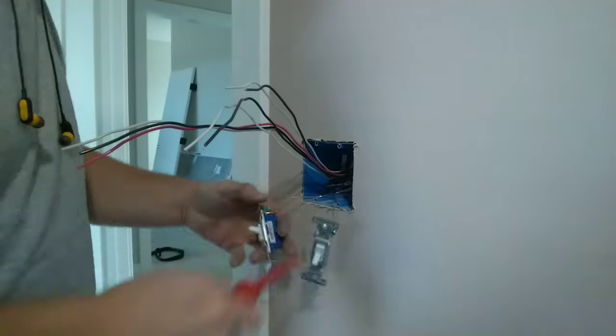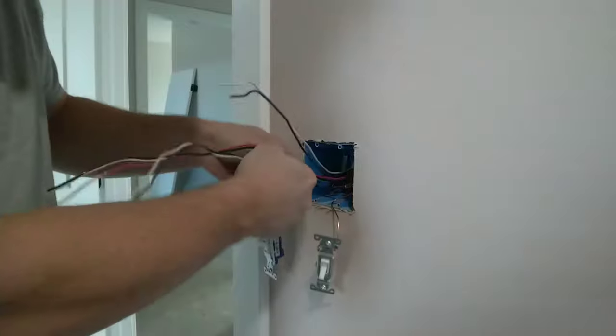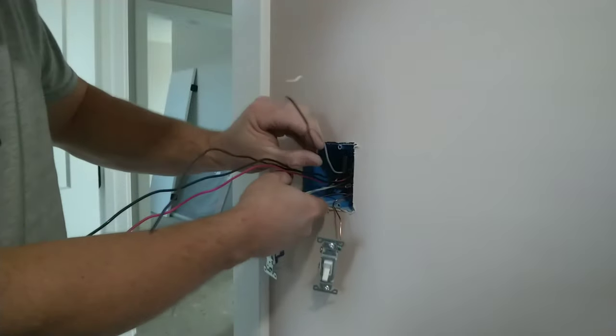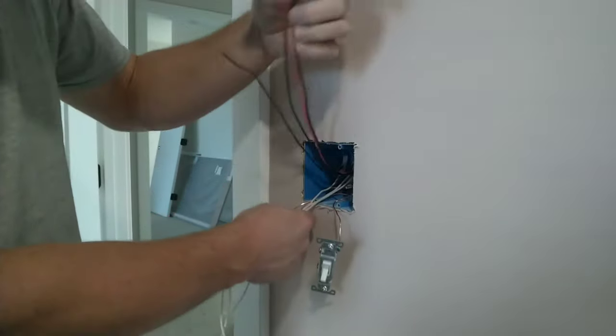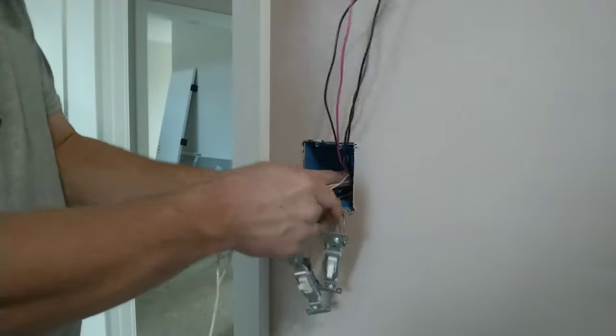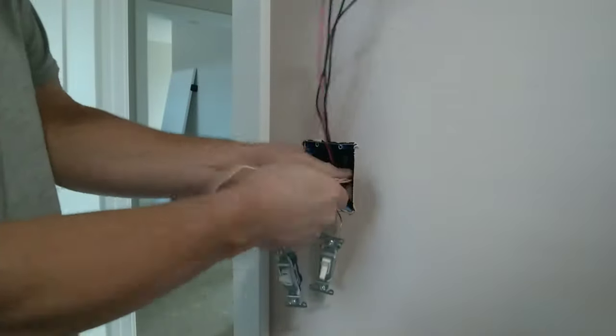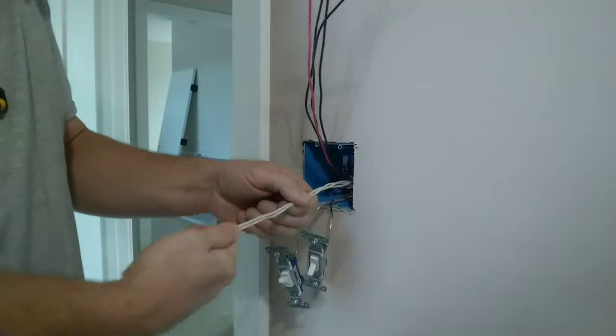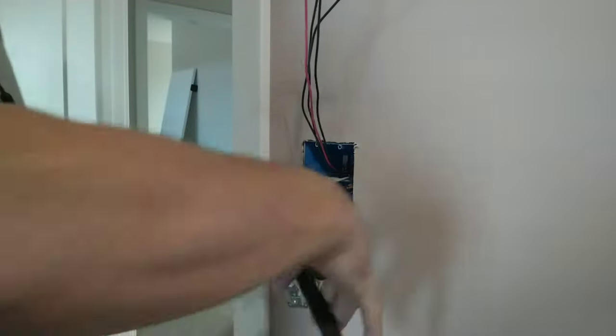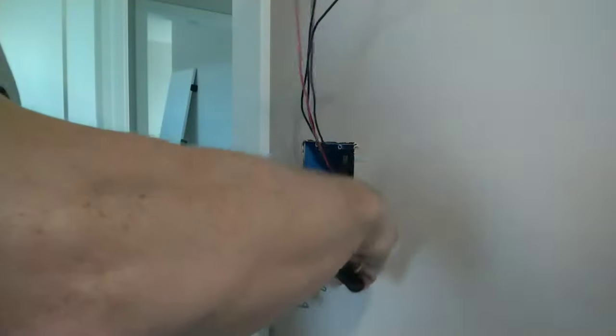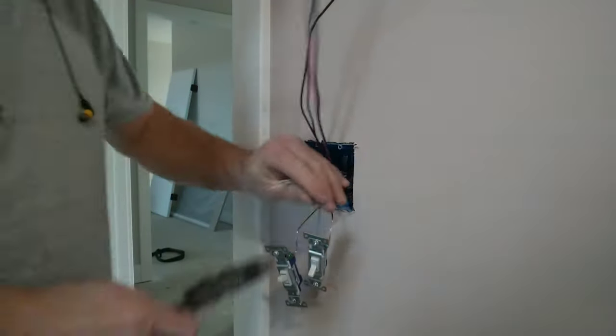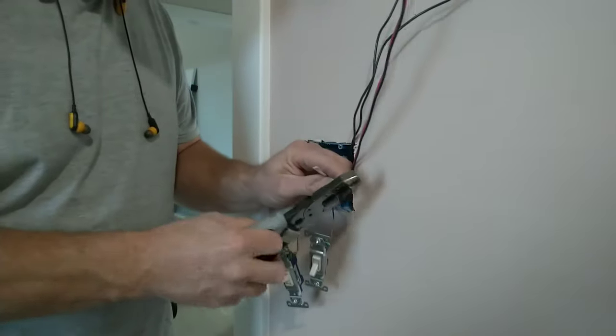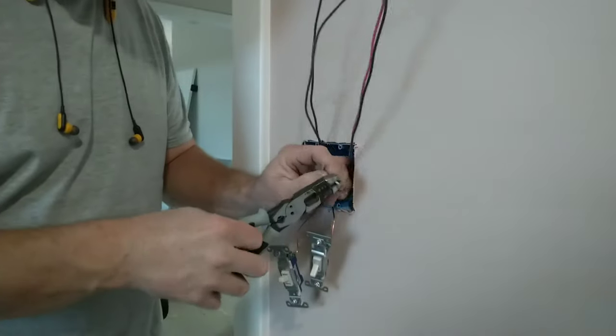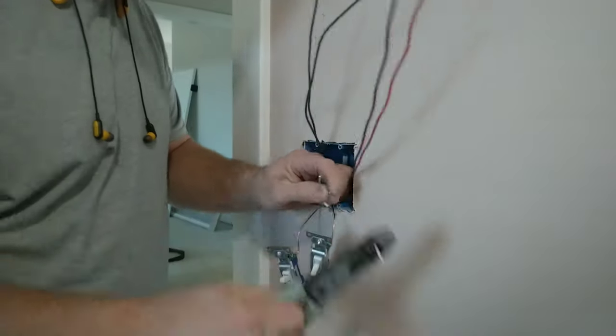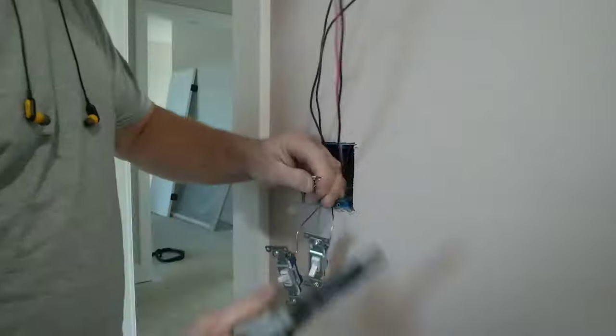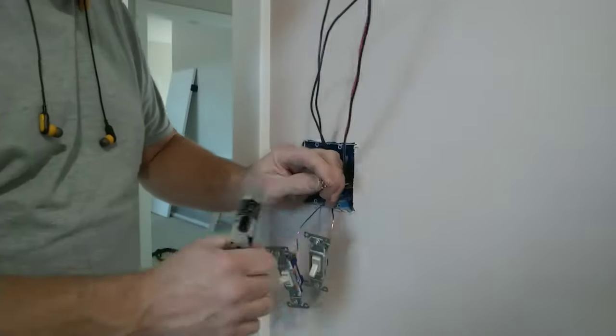Now we're going to work on our neutrals. Pull your neutrals to the bottom. Pull your hots to the top. Group them in the corner. Spin them, so you get a nice little light twist on. Cut it off. Now we're gonna strip back. We're gonna strip back 1 inch on each side. 7/8 to 1 inch.